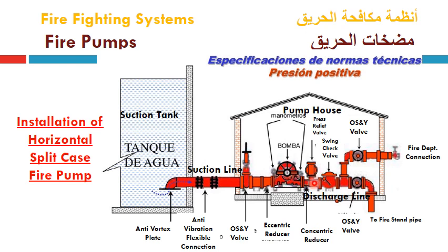Then the relief valve is located here to discharge the flow to the drain, or it may be back to the tank, the suction tank, in some cases. And then the swing check valve is located here, and this is its gate, and then the test hose to the fire department connection or hose valves, with an isolating OS and Y installed horizontally, and the main OS and Y gate valve on the discharge line for each pump, which isolates the pump from the fire stand pipe to be supplied with fire water to the protected zone.